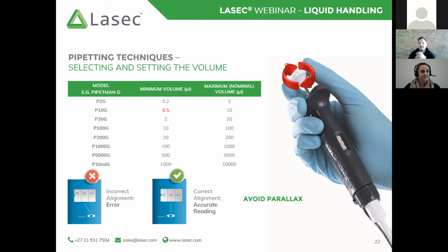In certain cases, the pipettes do have a sort of resistive volume setting mechanism. This is quite useful to allow you to feel when the volume has been set into the groove. But this is not common amongst every single pipette manufacturer. The other topic that we're going to discuss when setting the volume is the direction of that volume knob or thumb wheel. As a recommendation for improved accuracy and reproducibility, it is a suggestion that you always end in a clockwise direction when changing the volume.